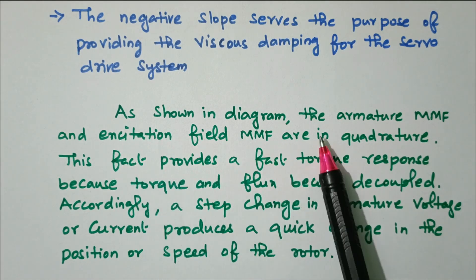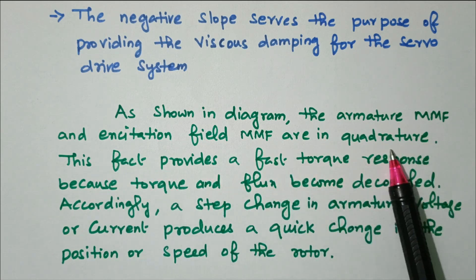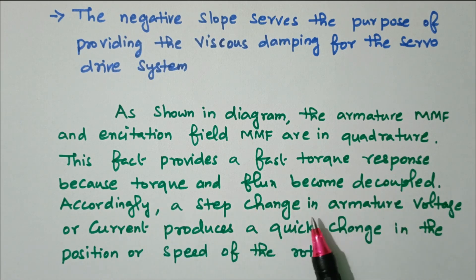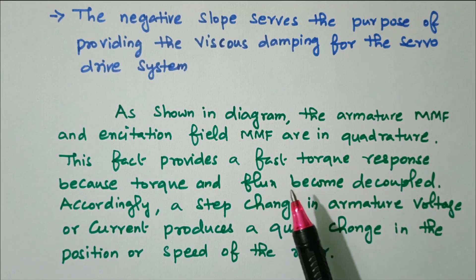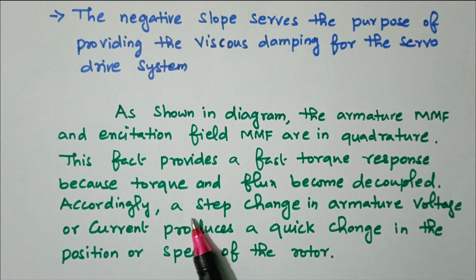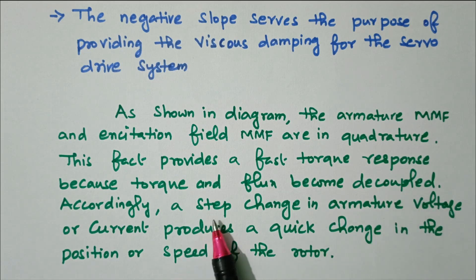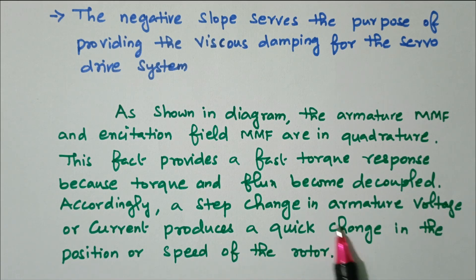As shown in the diagram, the armature MMF and excitation field MMF are in quadrature — 90 degrees. This fact provides a fast torque response because torque and flux become decoupled. Any small changes are reflected immediately. A step change in armature voltage or current produces a quick change in the position or speed of the rotor with no delay, which is why this motor is used for position control.